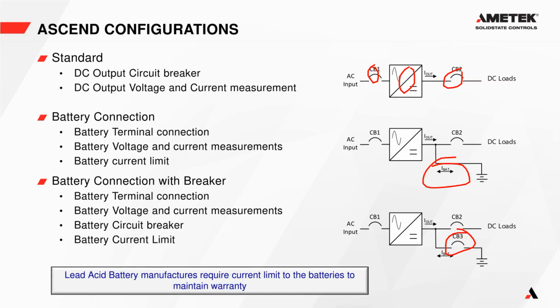Some of the other advantages you can get if you choose the battery current metering option is that, for one, you have a battery terminal connection right there at the charger, so you don't have to have a disconnect panel or some kind of breakout panel to connect the battery to your DC bus. And then it also allows us to limit the battery current to prevent overcharging or charging your battery too hard. So that's configurable on the display as well. And the battery connection with the breaker supplies the same thing, except it also has a low DC disconnect to disconnect your battery from your charger if battery voltage gets too low.